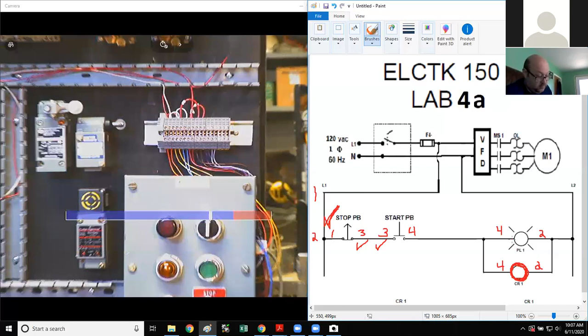So this wire number here, right here, is a 4. Does it matter which side of this I pull my other 4 from? Not that I'm aware of. No, because they're all in the same potential, right? So what I have landed on the wiring diagram is the start going over to the pilot light. Now I just need to make wire number 4 go over to the control relay coil, right? Yeah, I can take it from either one of those two points, whichever one I choose. Yep.